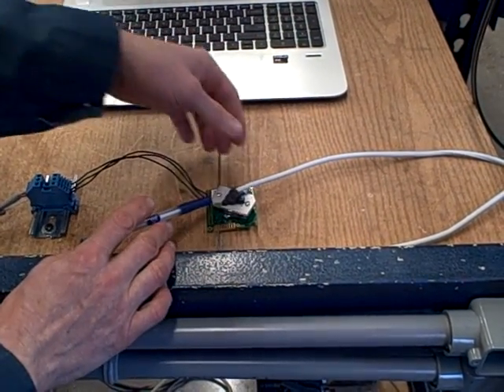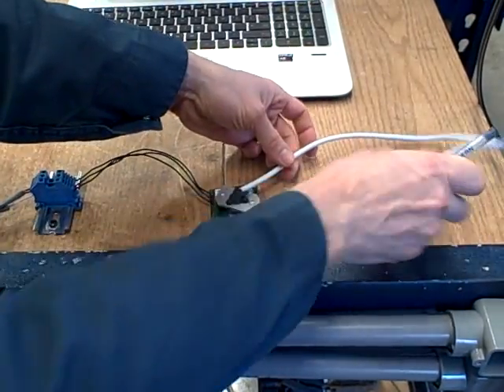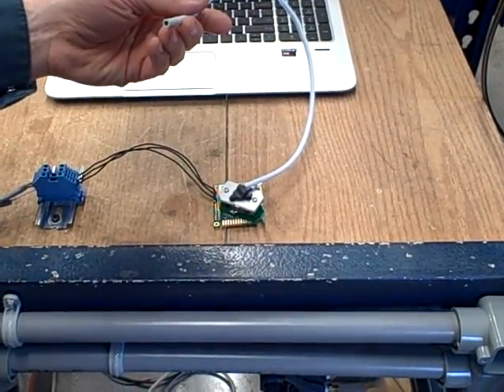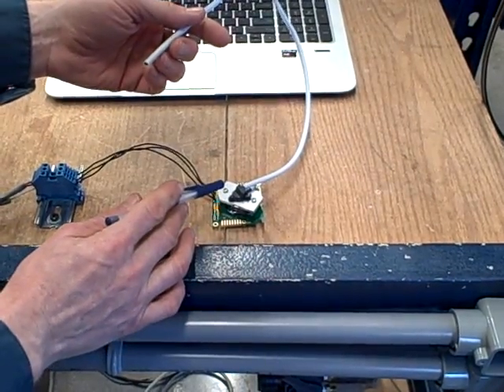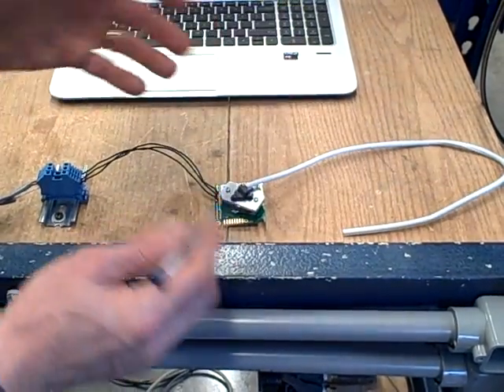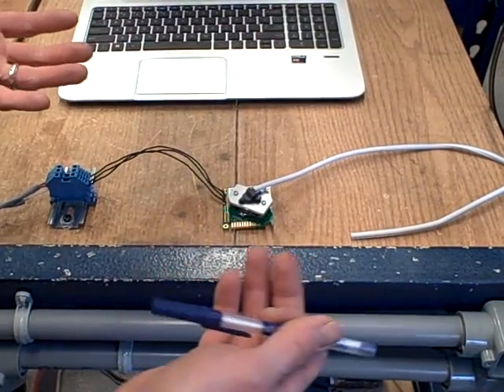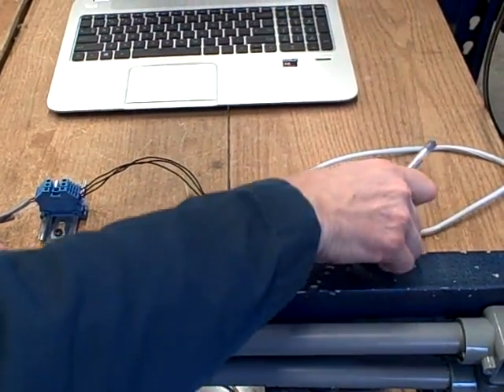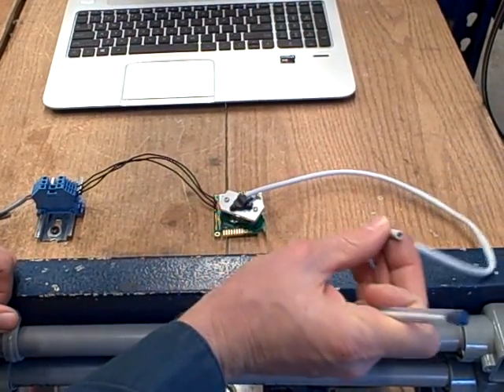This manifold that we have attached to it allows you to connect a hose and actually pass a sample of gas through the analyzer for analysis. If you don't have the manifold, it picks up the CO2 concentration through ambient air by diffusion, right through the membrane on the CO2 sensor. We wanted to be able to plumb this in to an external process, and so that's why we got the manifold.